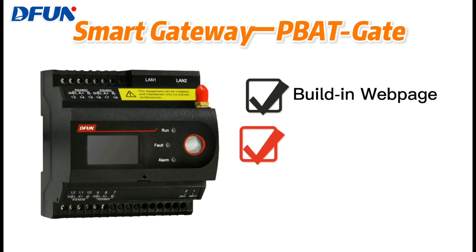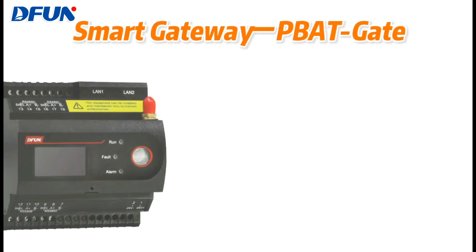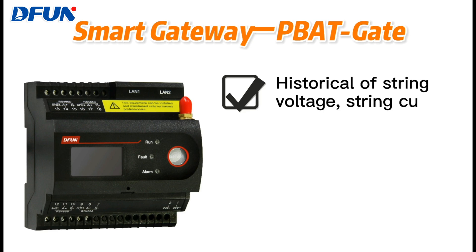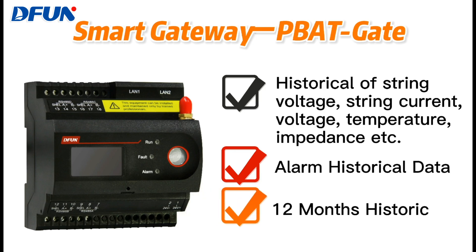It supports Modbus TCP and SNMP protocols for data uploading, as well as 4G communication. The PBAT-Gate can store historical data of string voltage, string current, battery cell voltage, temperature, and impedance, as well as historical alarms, and data can be stored in the gateway for 12 months.